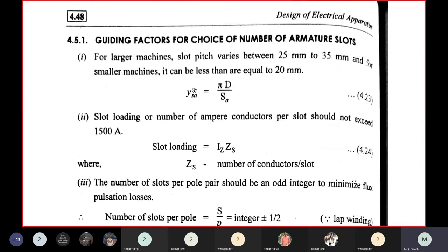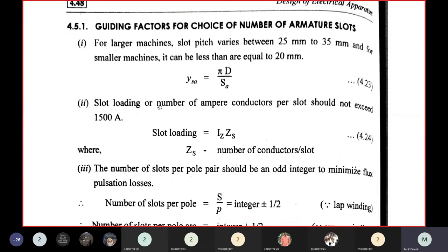Guiding factors for choice of number of armature slots: first guideline — for larger machines, slot pitch varies between 25 to 35 mm, and for smaller machines it can be less than or equal to 20 mm. The governing equation based on slot pitch is YSA = πD/SA, where D is the armature diameter and SA is the number of armature slots. The second guideline is that slot loading — number of ampere conductors per slot — should not exceed 1500 amperes.